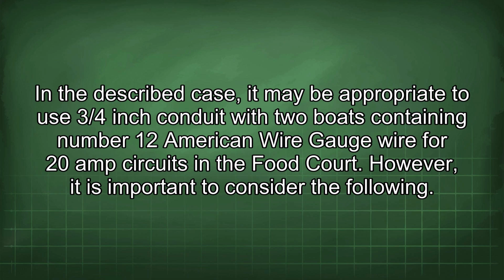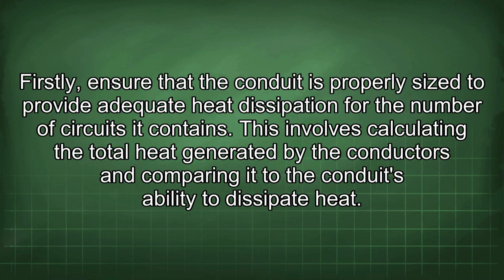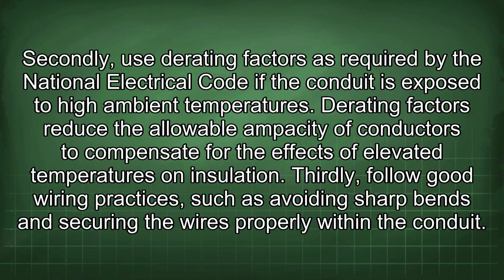However, it is important to consider the following. Firstly, ensure that the conduit is properly sized to provide adequate heat dissipation for the number of circuits it contains. This involves calculating the total heat generated by the conductors and comparing it to the conduit's ability to dissipate heat. Secondly, use derating factors as required by the National Electrical Code if the conduit is exposed to high ambient temperatures. Derating factors reduce the allowable ampacity of conductors to compensate for the effects of elevated temperatures on insulation.